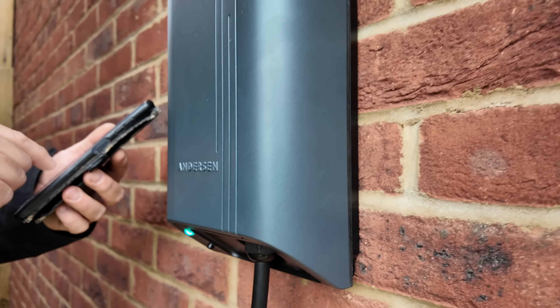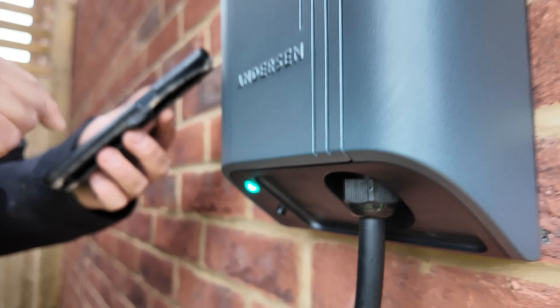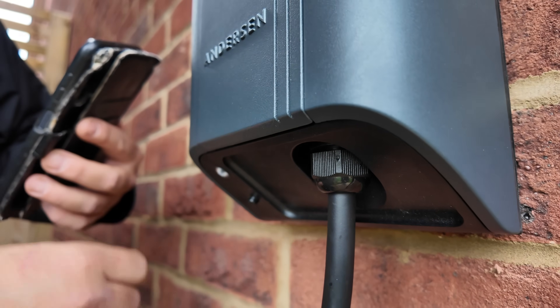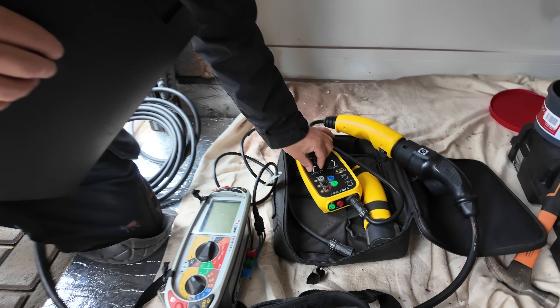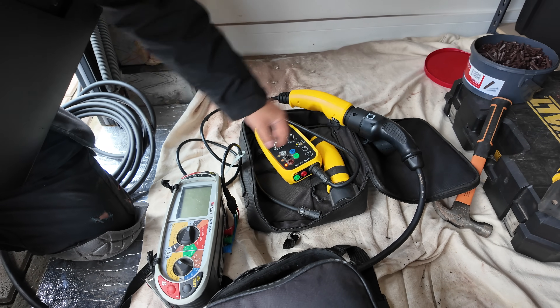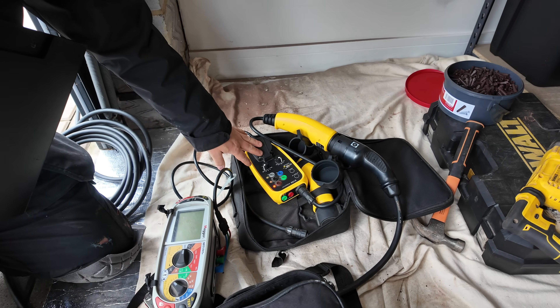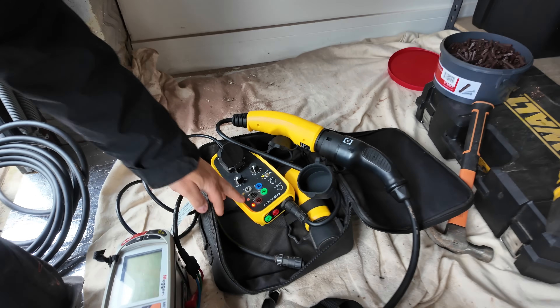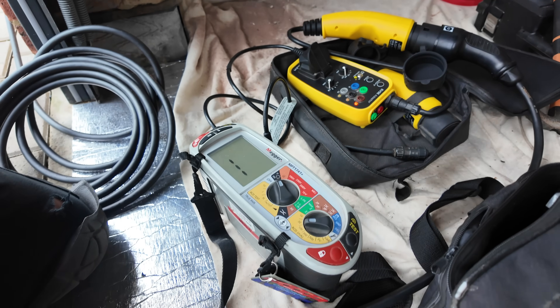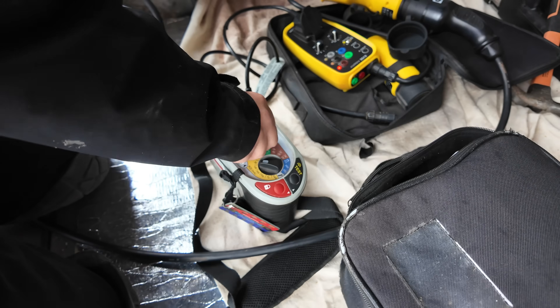That little button is a setup button. To get it into setup mode you press it three times and it'll pulse and flash blue. Press it once to come back out. I've got what's called an EV simulator or EV adapter — it simulates the car, so I can plug the connector from the charger into it, put it into charge mode to get a light on showing the charger is working. From there I can test voltage, earth fault loop impedance, and the RCD.